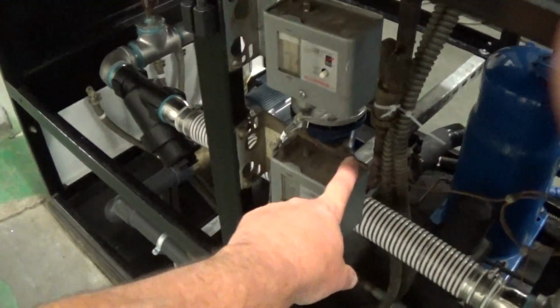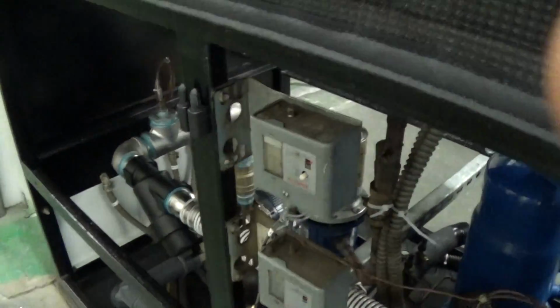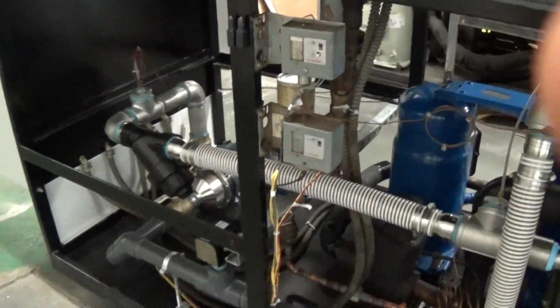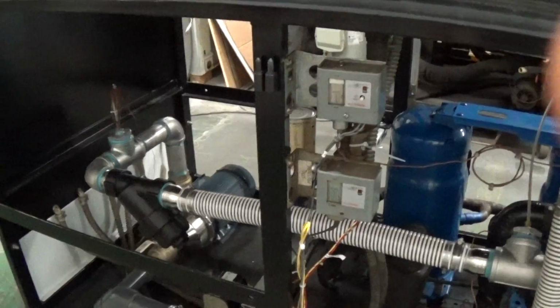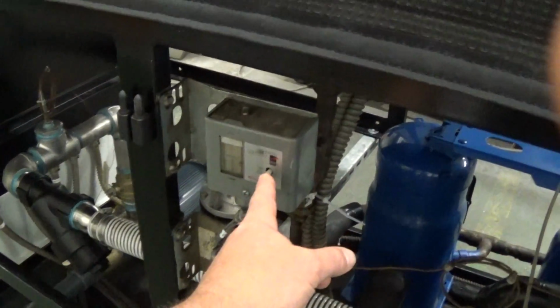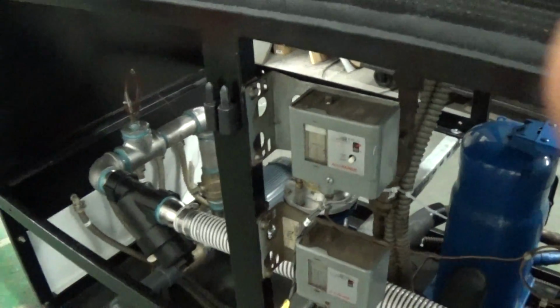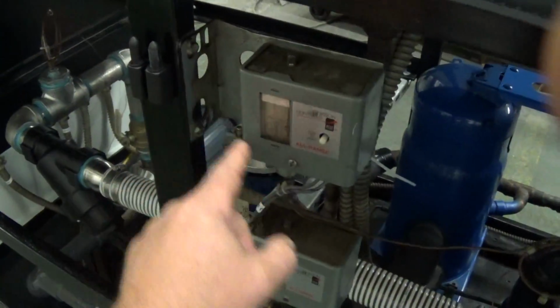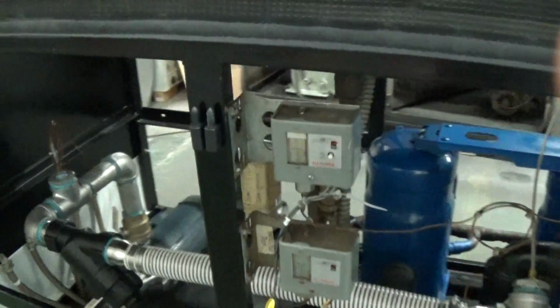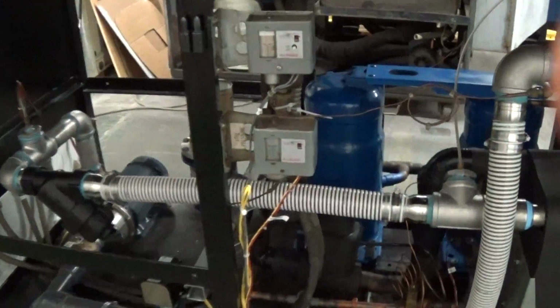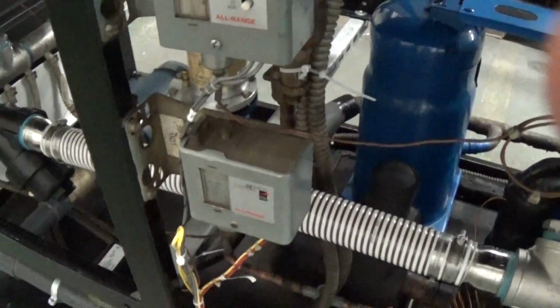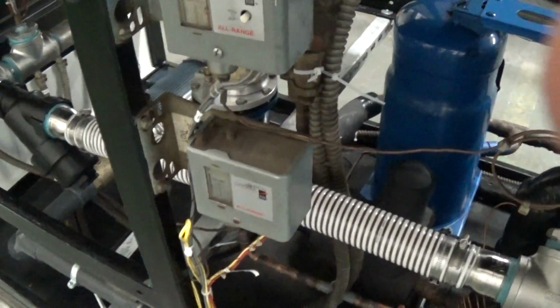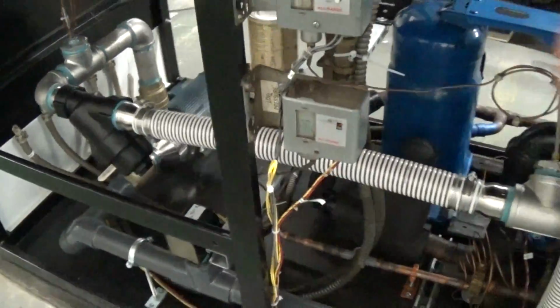Here we have your low pressure and high pressure refrigerant switches. You don't have to touch those. Don't play with those. This one here, if anything were to happen, that's the low pressure, that's the high pressure. This one does have a resettable switch. An example of a low pressure would be if you're running the water temperature too cold, or if you're not getting enough flow over your exchanger.